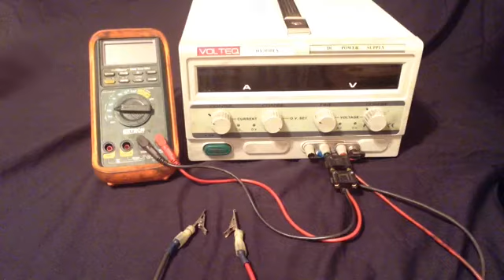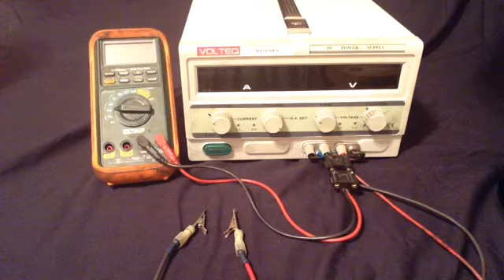That's why you need separate probes for your voltmeter, and that's the reason for the 4-wire connections, also called Kelvin clips. So here is the correct way to connect the leads: one set from the power supply to the Kelvin clips, and the other set from the meter to the Kelvin clips. That gives you your true 4-wire connections.